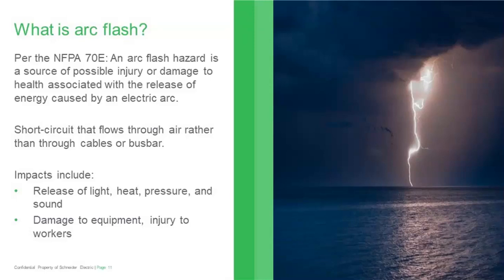Heat is what we think about probably the most with these events. We look at incident energy levels in calories per centimeter squared and figure out what type of arc-rated PPE to wear. But the other things can be real hazards as well. Certainly there can be enough energy to cause significant damage to equipment and injury for workers who are unfortunate enough to be caught up in one of these events.